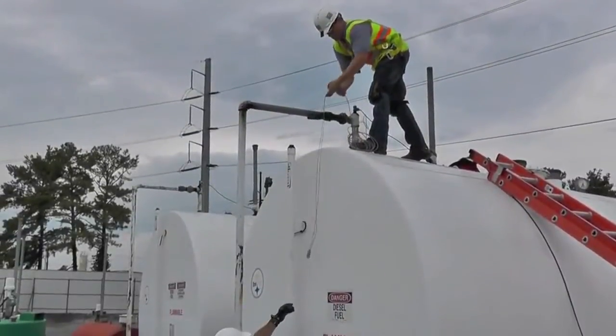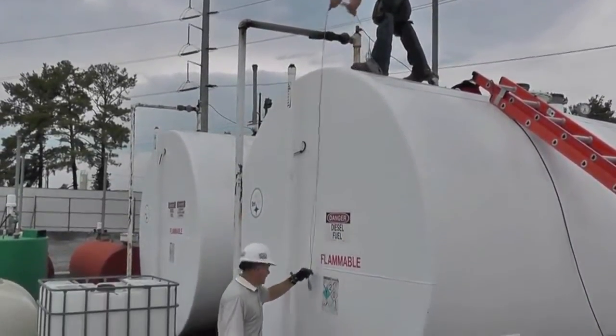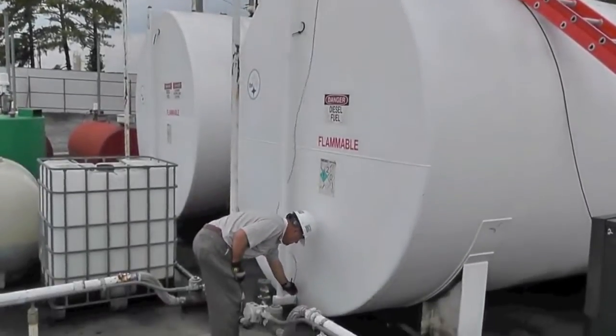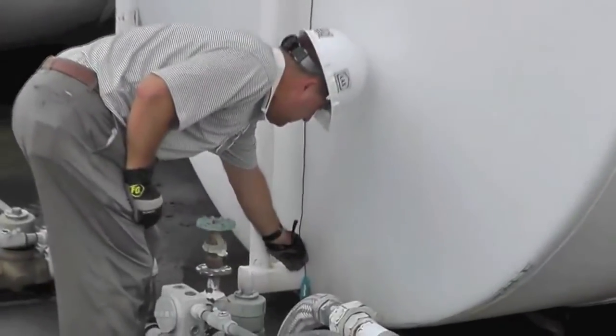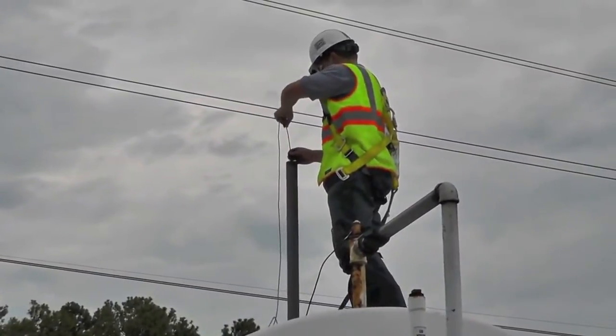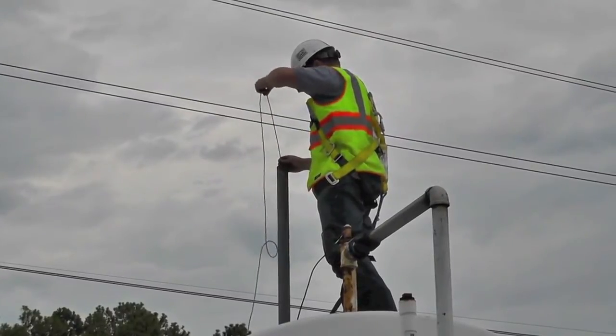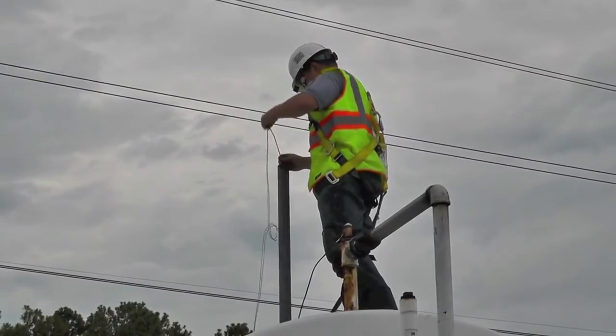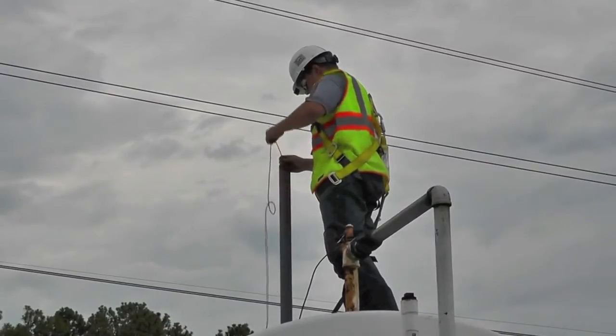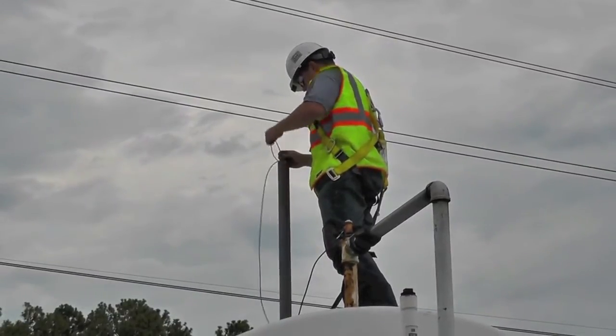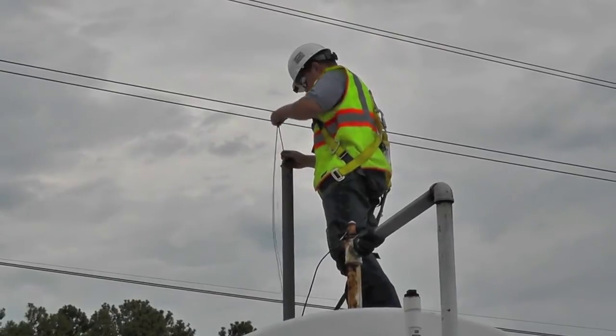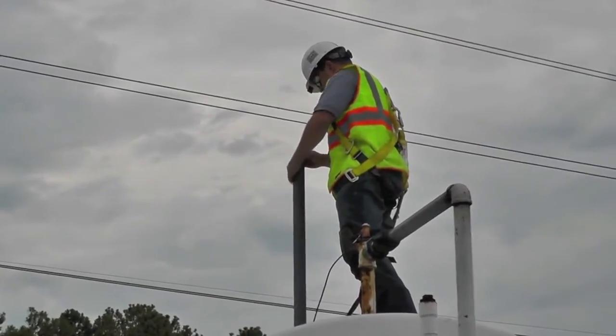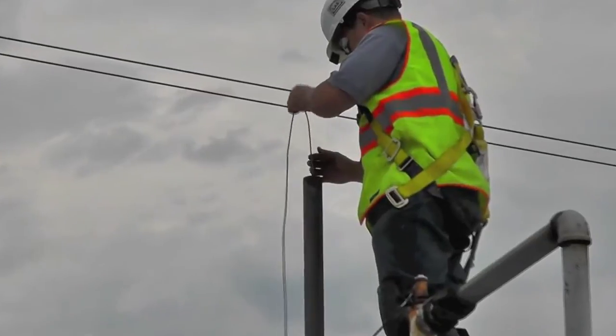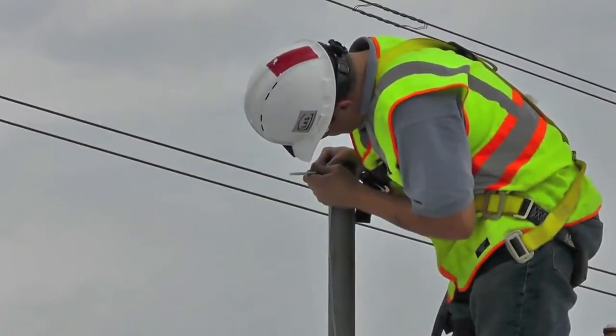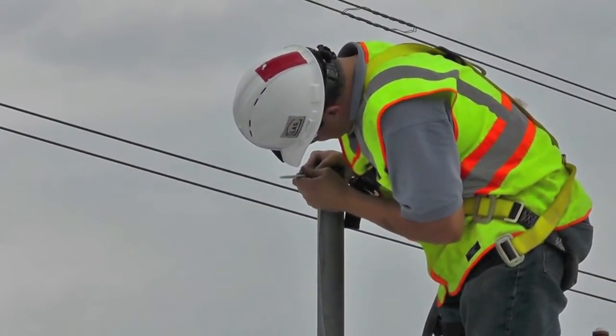Once the cap is prepared, we can then measure the external height of the tank, including the length of the breather tube, so we can cut the excess cable. After the cable is measured and cut, we will then lower it into the tank until it hits the bottom. At this time, we actually raise the cable just slightly off the bottom to avoid contact with any sludge or buildup at the bottom of the tank.